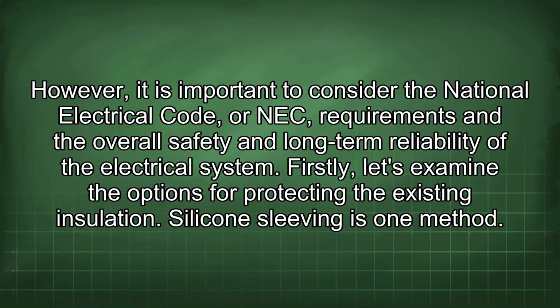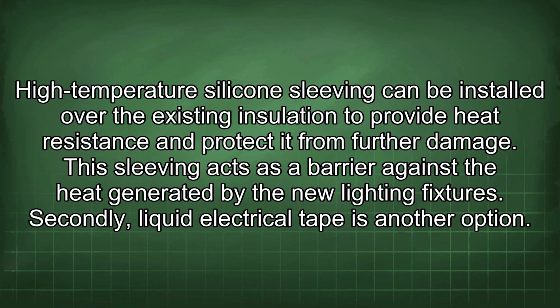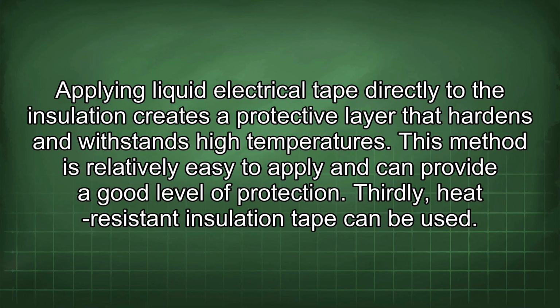Silicone sleeving is one method. High-temperature silicone sleeving can be installed over the existing insulation to provide heat resistance and protect it from further damage. This sleeving acts as a barrier against the heat generated by the new lighting fixtures. Secondly, liquid electrical tape is another option. Applying liquid electrical tape directly to the insulation creates a protective layer that hardens and withstands high temperatures. This method is relatively easy to apply and can provide a good level of protection.